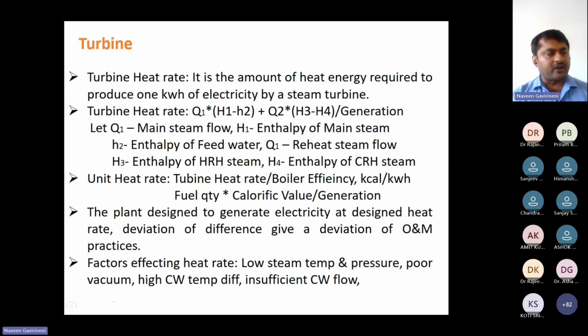I'm going a little faster because of the time limitation. So this is the formula for calculating the heat rate: mass of steam into the enthalpy of steam minus the enthalpy of feed water, plus mass of hot reheat steam into the enthalpy of HRH minus the enthalpy of CRH, divided by generation. Just go through that. These are the main factors on which heat rate depends: low steam temperature and pressure, which I already explained while explaining the boiler, poor vacuum, high cooling water temperature difference, and insufficient cooling water flow.